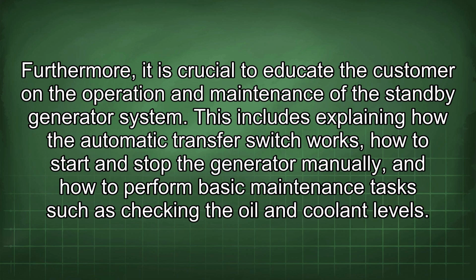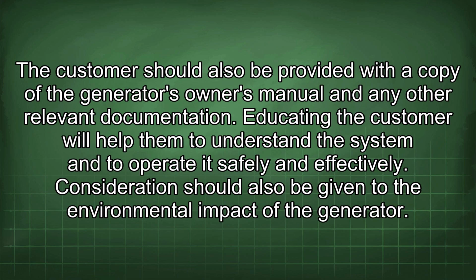Furthermore, it is crucial to educate the customer on the operation and maintenance of the standby generator system. This includes explaining how the automatic transfer switch works, how to start and stop the generator manually, and how to perform basic maintenance tasks such as checking the oil and coolant levels. The customer should also be provided with a copy of the generator's owner's manual and any other relevant documentation. Educating the customer will help them to understand the system and to operate it safely and effectively.